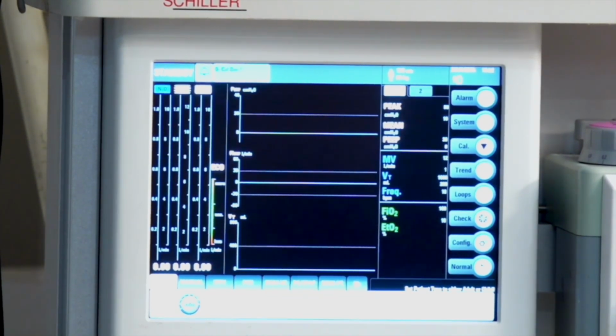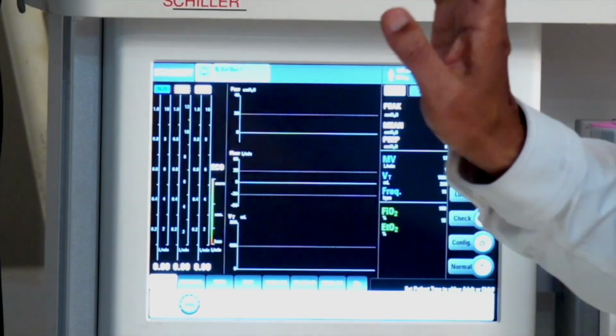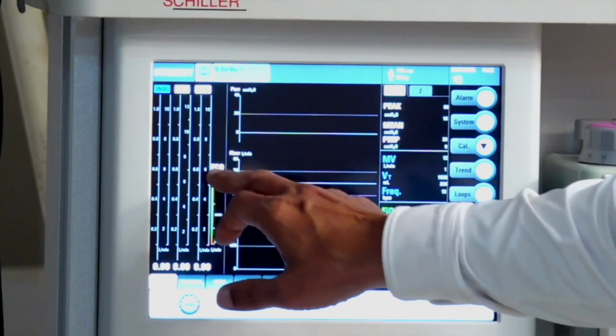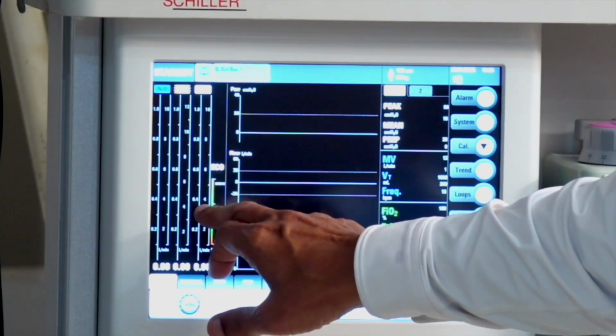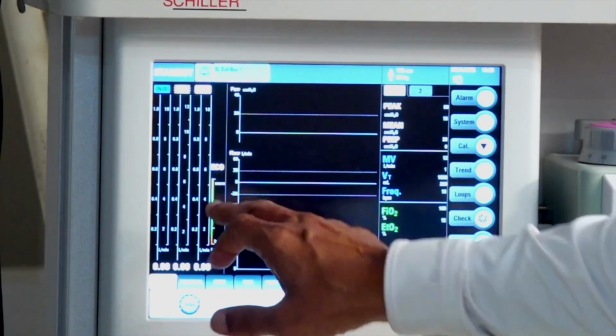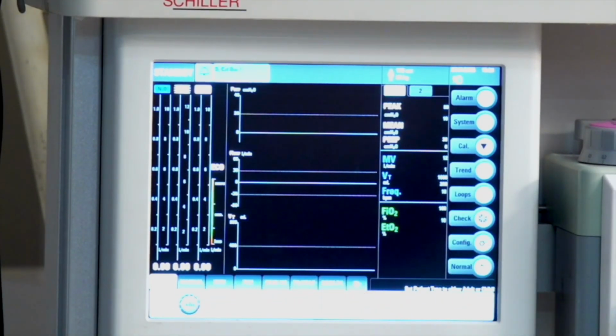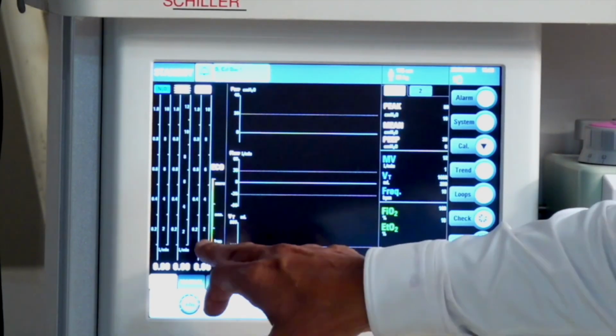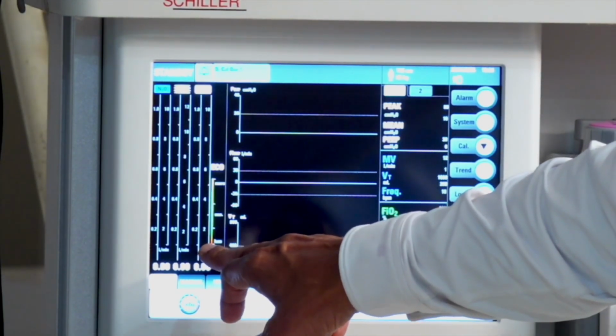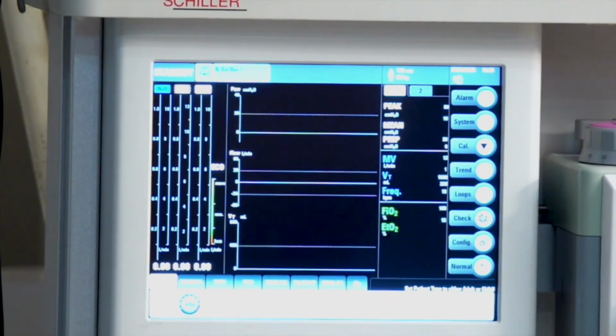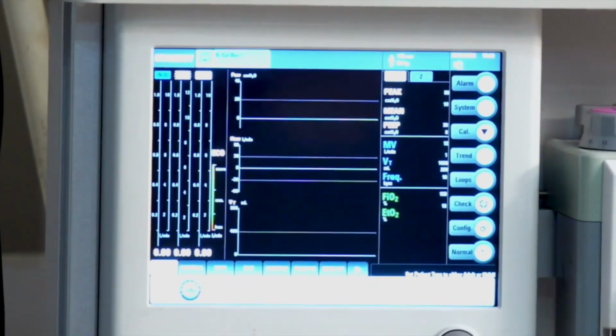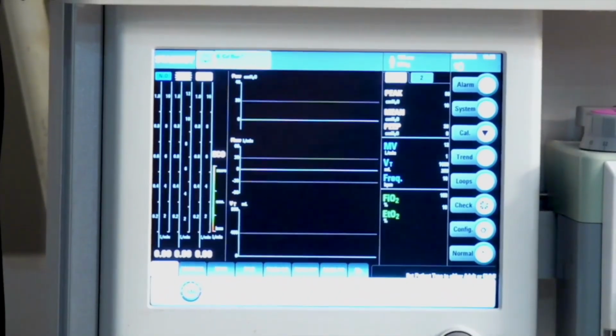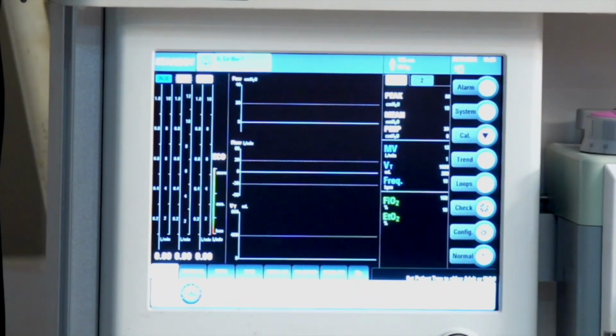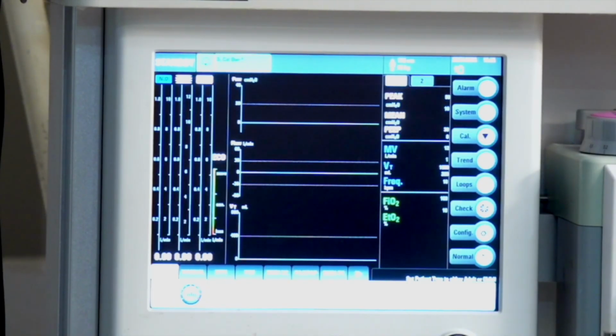So the moment you go beyond 2 liters, it will reach only up here. When you are around 1, it will start coming down. And of course, if you go to 0.5 and it is efficient, it will remain here. But if you are really reducing the flow much below your oxygen consumption, it will go down to red, and it will tell you that you are giving insufficient flow. So that's an advantage, and almost all companies have one way or another of doing it. I think that's all. If you have any queries, we can still solve them or discuss them.